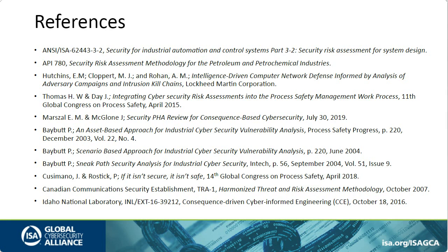With regard to once you're in operation, there's two things. One, you'll typically set an interval, and I sort of talked about process safety management regulations saying no greater than 5 years. Some argue that because cyber is so dynamic and evolving that it should be done more frequently, but yet there's no standards out there that provide any guidance as to the actual timing.